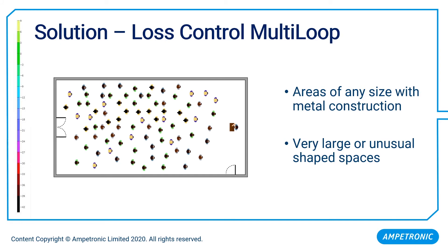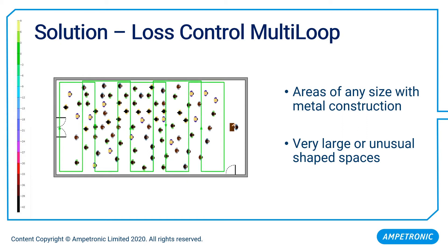So what can we do about this? The typical problem — that black hole in the middle of the room — is the behavior associated with a perimeter loop installed in a room with metalwork present where the loop is too big for that to be a safe approach. The solution is instead of having one big loop, we install several smaller ones. An array of, say, five smaller loops each perhaps three meters wide in the narrower dimension — we put as many as needed to fill the room. Over each of those five individual loops, we get good performance irrespective of any metalwork present.